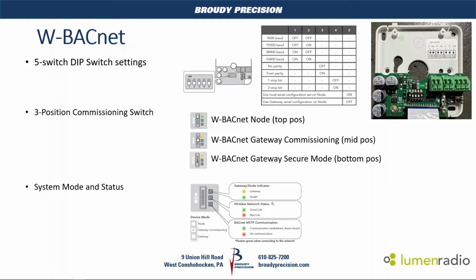You can see there's a 3-position switch here in the bottom right, and there is also a reset button that you use to wake the LEDs. There's also a procedure if you had to do a factory reset, you could use the button for that as well. The 3-position switch is set up like this. The top position is, if it's a node, you set it there. If it's a gateway and you're doing your commissioning for the first time, you set it to the mid position. Once commissioning's done, you set it down to the bottom position. At that point, it will secure that mode and the system is set up and operational.